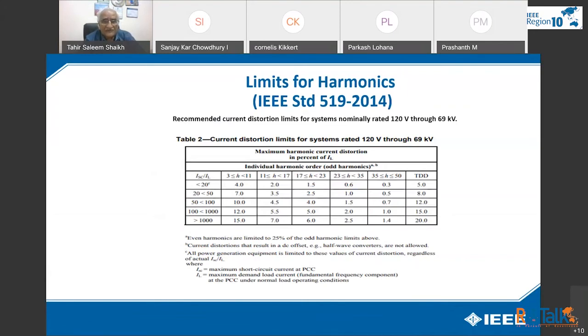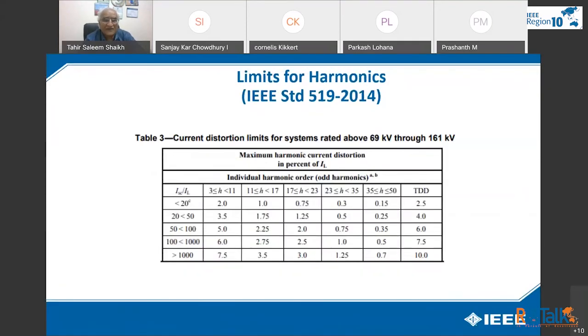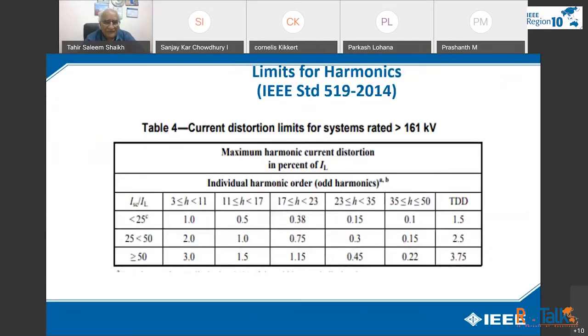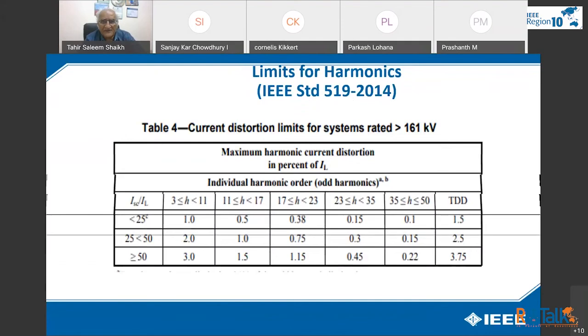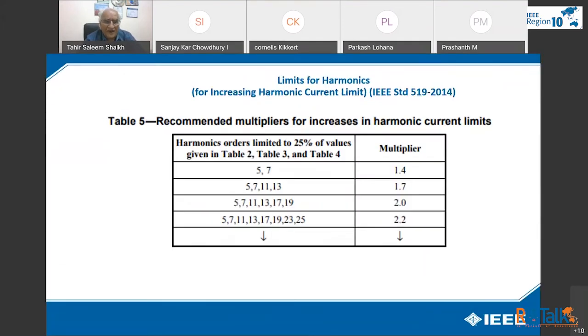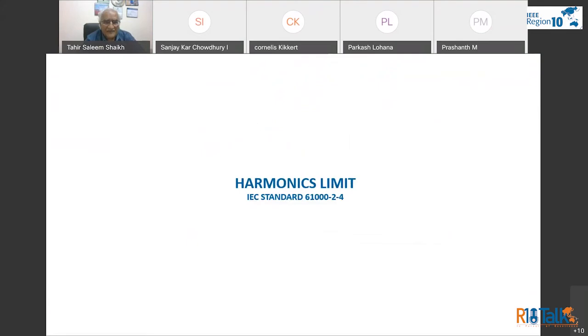So you have to operate either as a renewable energy or conventional energy within these limits, so as to avoid any defects in the equipment. Maximum harmonic current distortion, what should be there? This is the ratio given over there, distortion in percent of IL. So I will give you the chart. Maximum harmonic current distortion percentage of IL, total current distortion limit for system rated high voltage. Harmonics order limit 25% of the value given in table 2, table 3, and table 4 for that particular standard and codes.